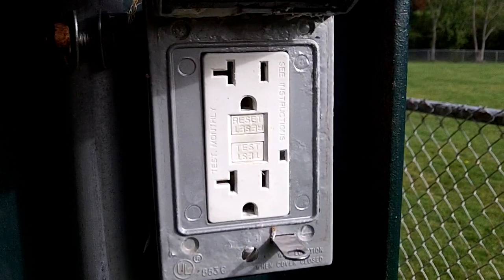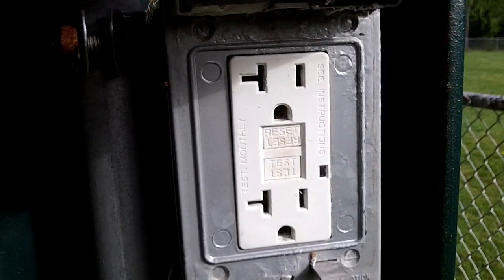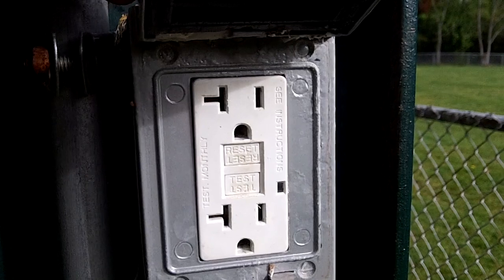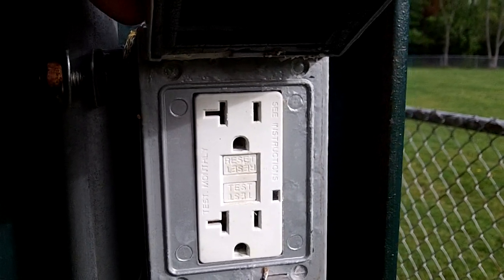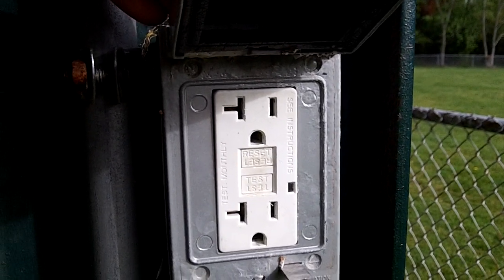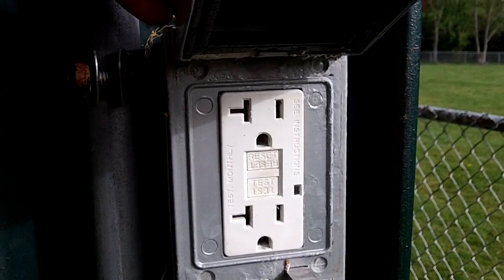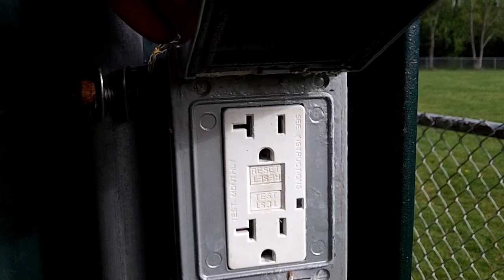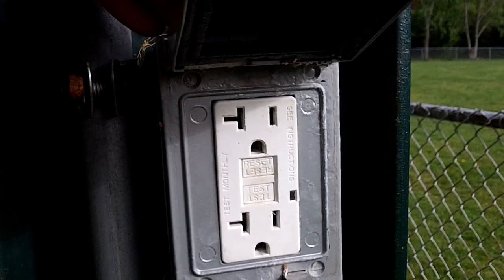Also, this plug needs to be a weather-resistant type, and as you can see it's just a standard type GFCI — it's not weather resistant. So we have the wrong type of cover and the wrong type of receptacle in this application. This is Russell Blank, NEC consultant for EC&M magazine.